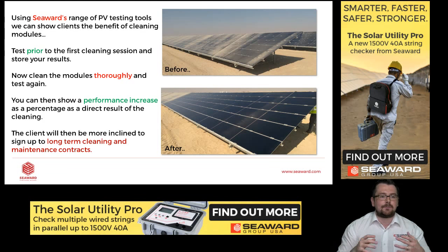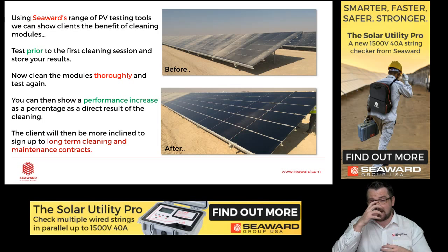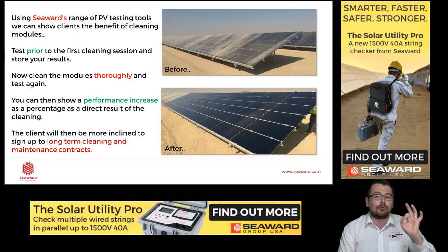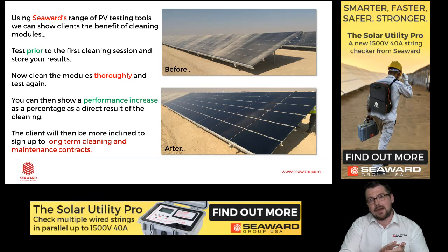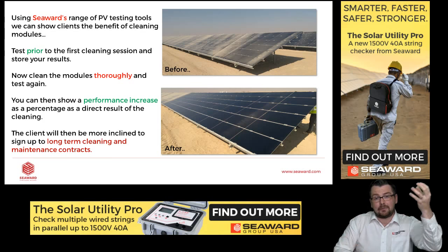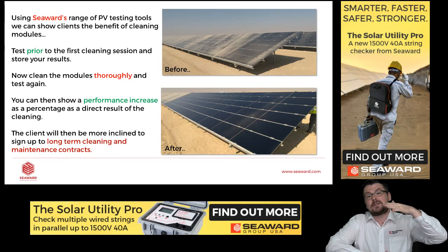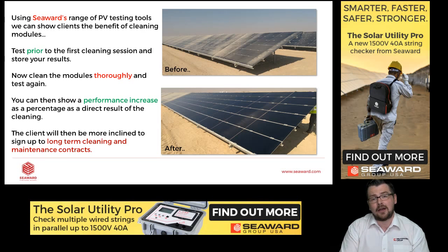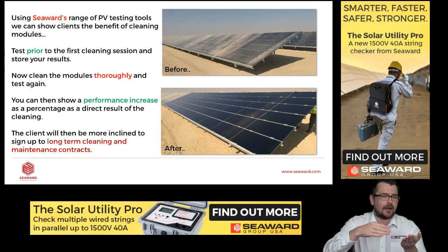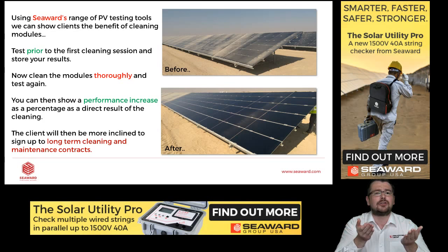So what we can do is, by using the Seaward or the Solmetric range of test tools, we can test prior to the first cleaning session. So we test when they're dirty and we measure the result. And then we clean the modules thoroughly, and then we can test again. Now the difference between the before and the after cleaning, we can do this as a percentage. And then we can go to our clients and say, hey, Mr. and Mrs. Smith, I've cleaned your modules. This was the output I got prior to cleaning. This was the output I got after cleaning. This was 10, 20, 30%.